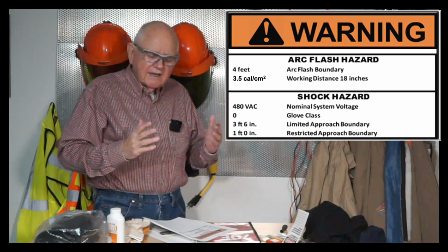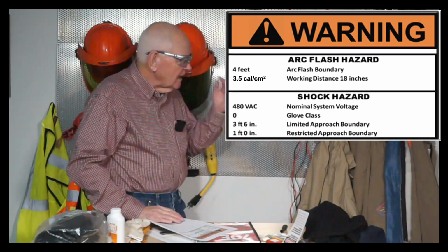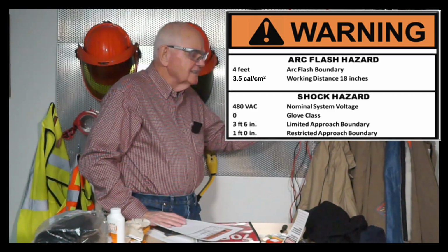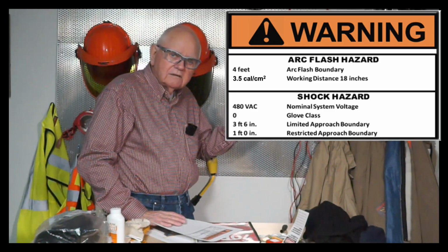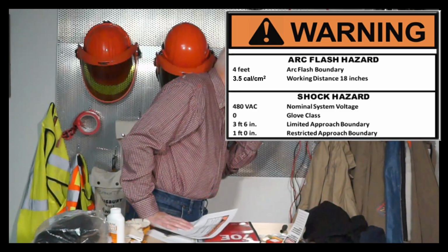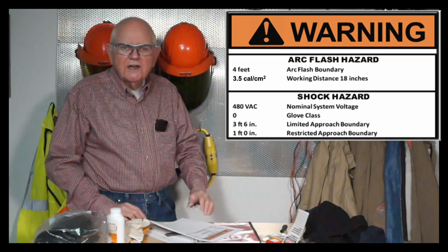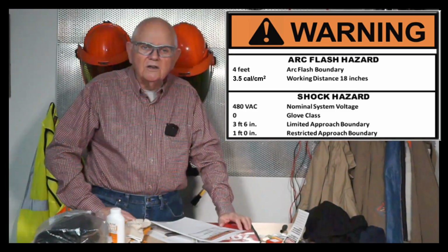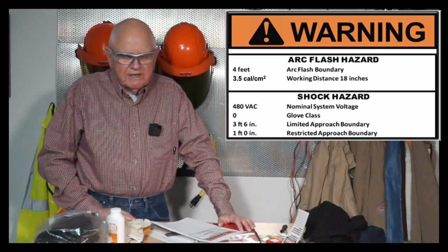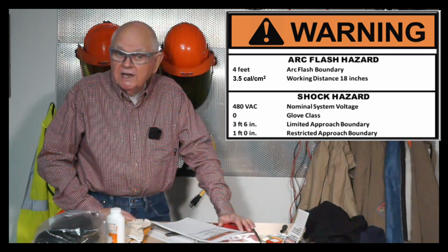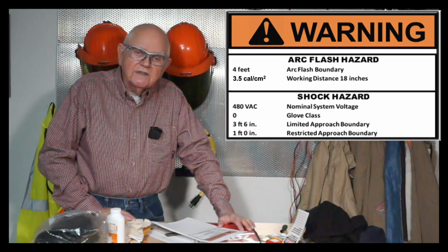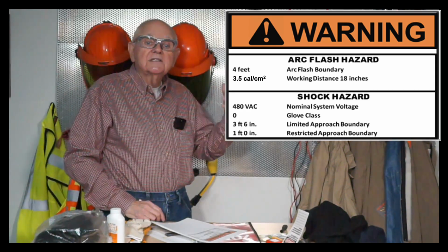That means the calculation is 3.5 calories per square centimeter at a distance of 18 inches away. So if I need to stick my head inside of that 18 inches and go down to 9 inches to read the wire label or something like that, how many calories should I protect against? And the answer is we don't know. We'd have to do the calculations. The values do go up exponentially.